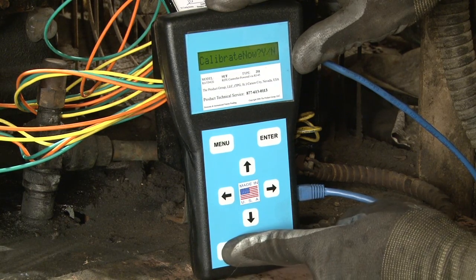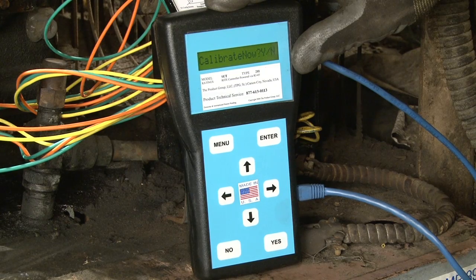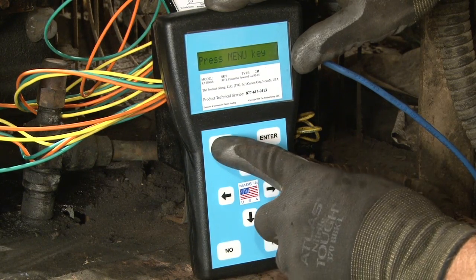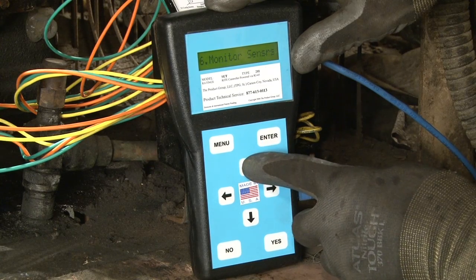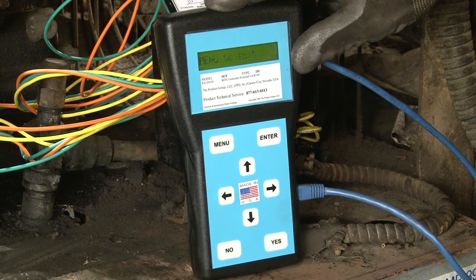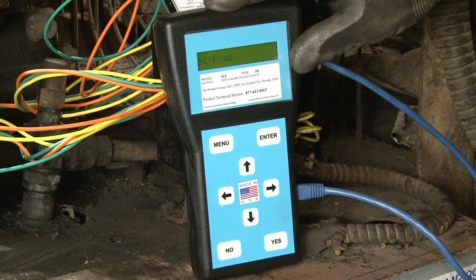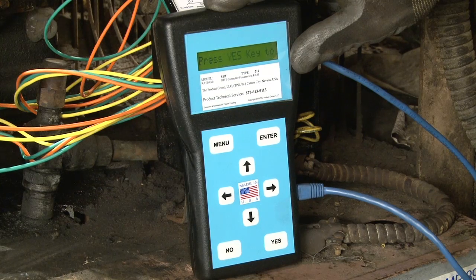It also asks us if we want to calibrate now. We've already calibrated the sensors, so we say no. Notice we've now returned to the main menu screen. We'd like to see what the transducers are doing, so we move to item number 6 to monitor the pressure transducers and what the system is doing. As you can see from the screen, it makes a continuous scroll telling us what the current readings are, whether the relay is on and off, and what all 4 channels of the transducers are doing. We may at any time press the menu button to return to the main menu screen.